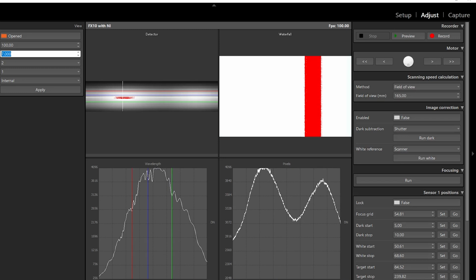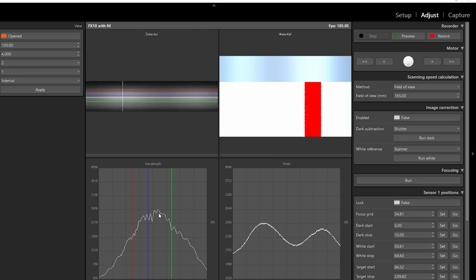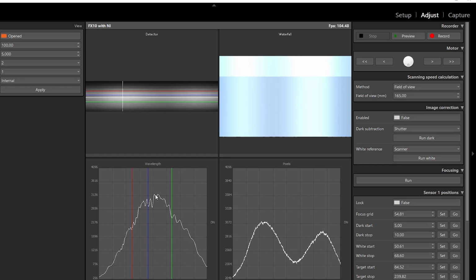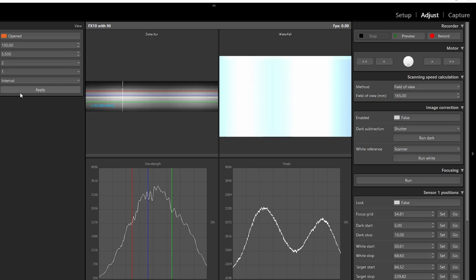So if I put something which is too low, then I don't use the best of the camera in terms of signal to noise ratio, because it's the same as if I will open my eyes but not long enough to acquire enough photon to be able to really separate or to acquire good images. So here 4 milliseconds is a bit low. If I put 5 milliseconds, I will reach about 3200 digital number out of 4096. I think we can put 5.5, it is going to be something quite relevant.